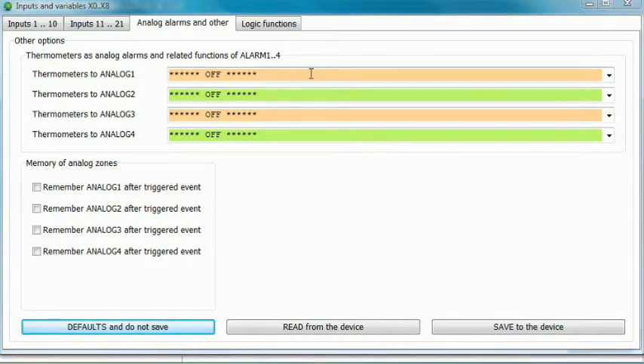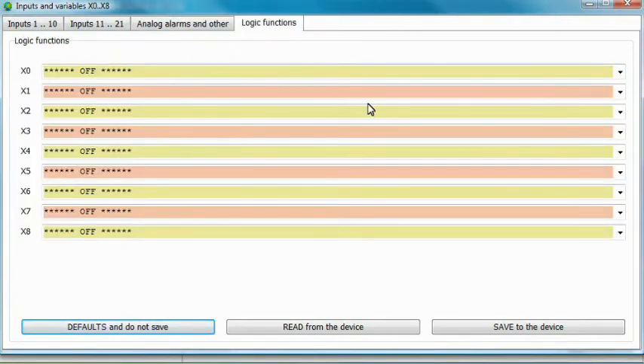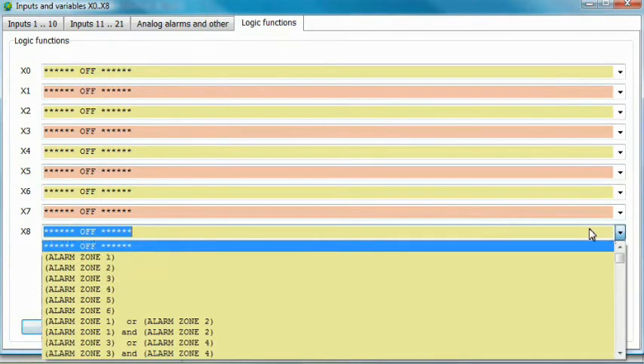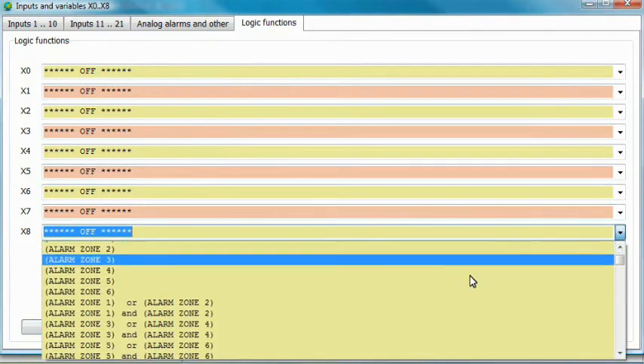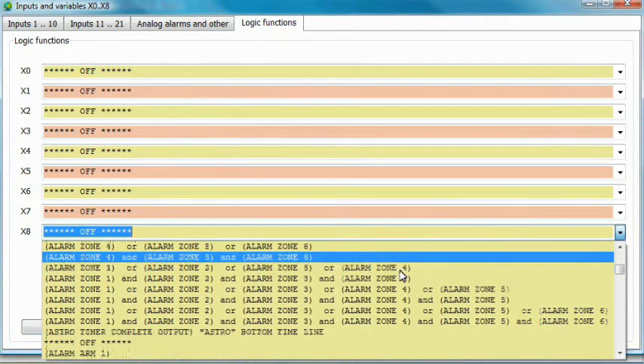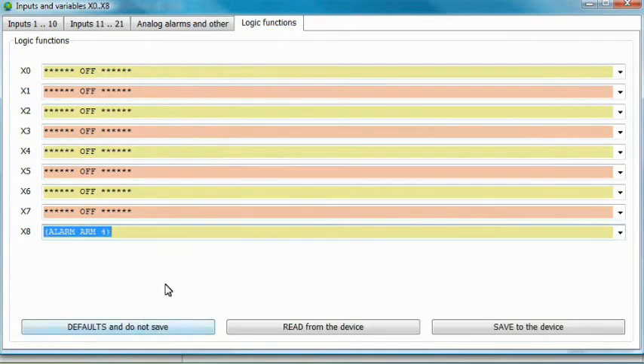Let's switch to the Logic Functions tab. This works similarly to the programmable relay. For instance, let's take variable x8. You can configure it so that it activates when one of the alarm zones is armed. Save the configuration and see if this works.